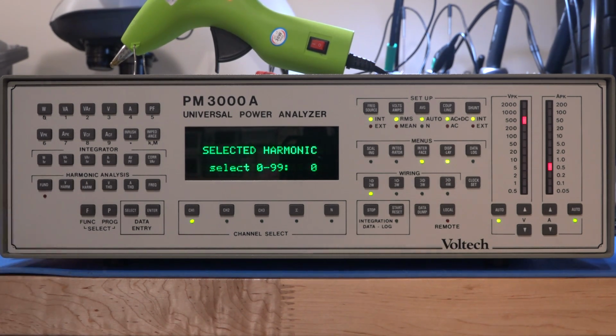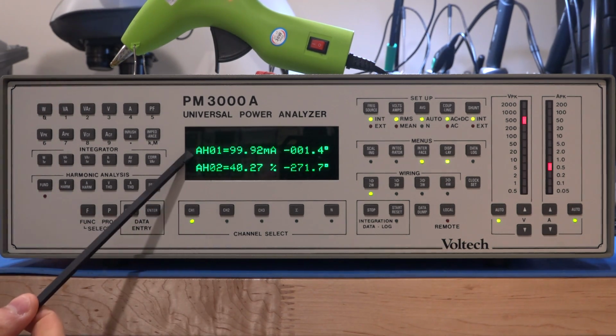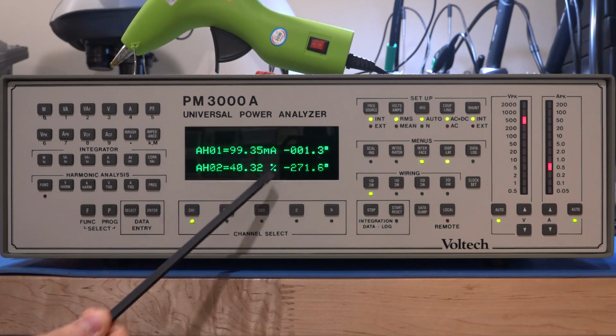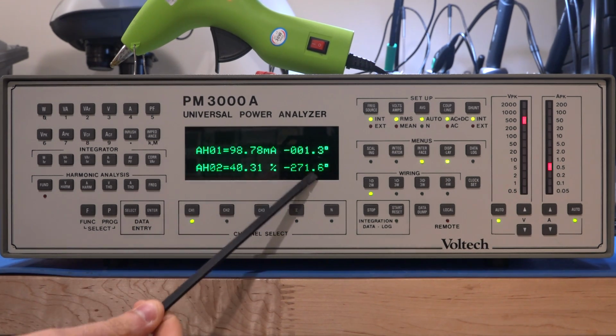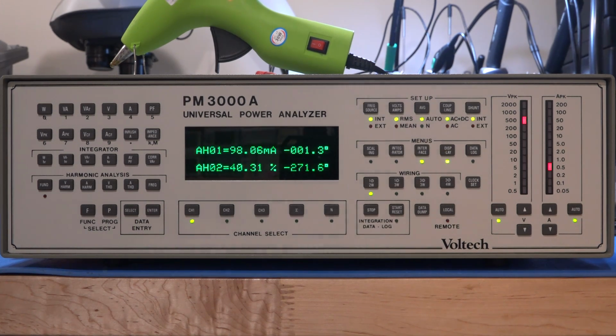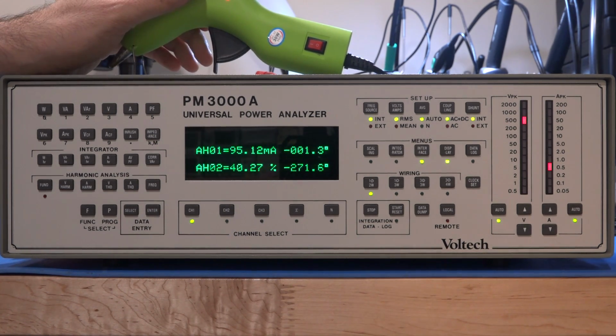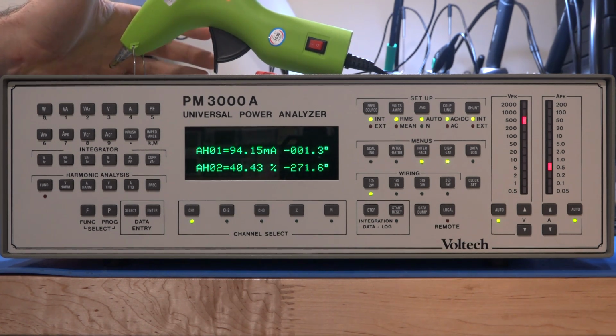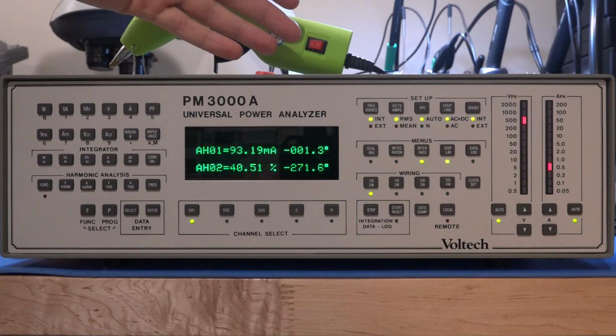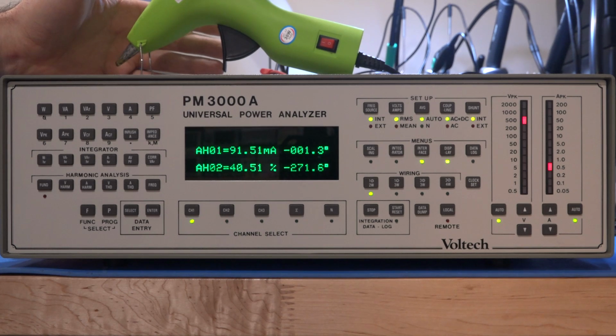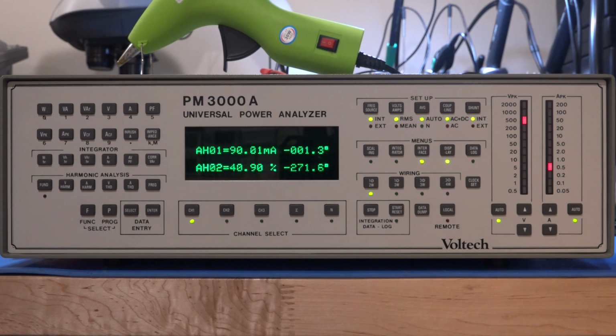We can look at that. We can go under A harmonics, and we can select which harmonic we want to look at. So I'm going to look at the second harmonic, press enter here, and you can see that the fundamental harmonic is drawing 99 milliamp, whereas the second harmonic is 40 percent, and you can see the difference between the phase of those two. So indeed it is producing a fairly poor current waveform, and you can see the different phases of the various harmonics. So why is that? That's because this thing actually has a triac inside, and some of the power control is done by a triac. I cannot adjust anything. This only has a power on and off, so you're going to get a better look at it. So really, this kind of device in here, this triac in here, is going to create a weird waveform. So this is not a simple resistive component anymore, which is, I think, quite interesting.